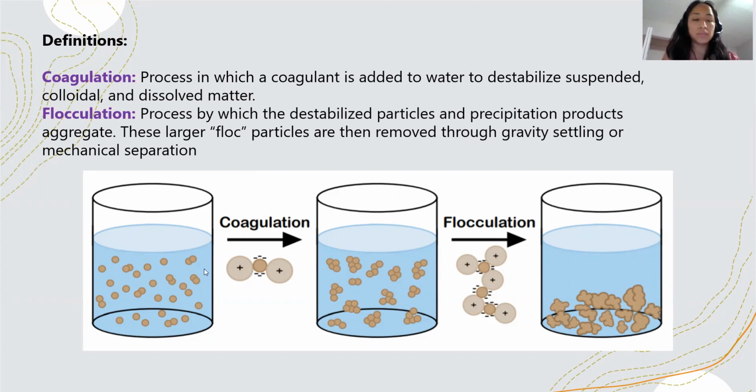And the coagulation involves a rapid mix, so 2 minutes at most for the coagulant to react. And then the flocculation implies a really low speed and maybe a longer time, like 20 minutes. And then the settling could be from 30 minutes to 1 hour.